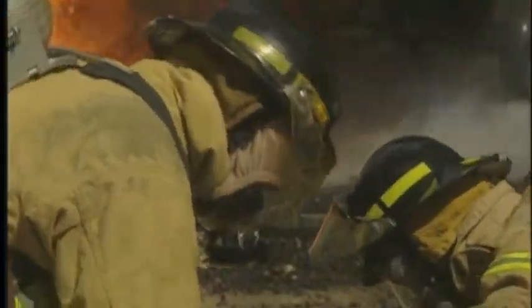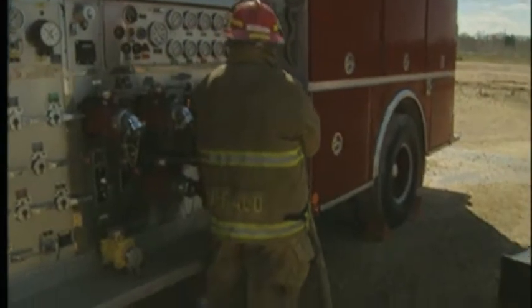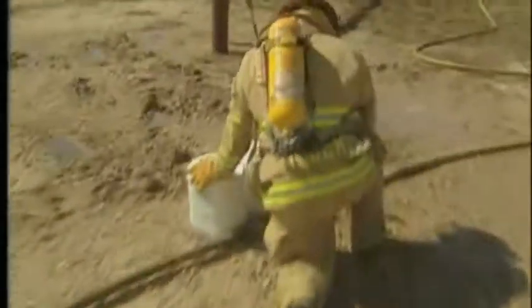In a flammable liquid fire, it is the vapors that burn, not the liquid fuel. This concept is important for understanding how foam works. Foam is simply made. Start with water and add a measured percentage of foam concentrate. Air is then mixed with this foam solution in a turbulence chamber, expanding its volume.